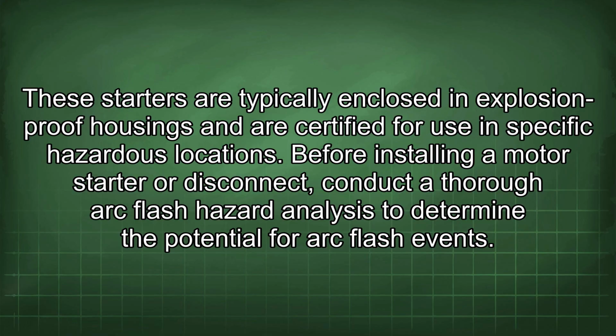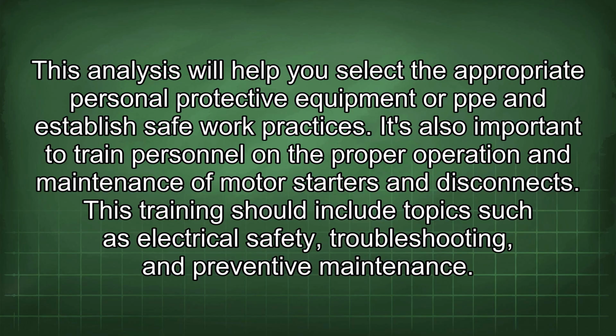Before installing a motor starter or disconnect, conduct a thorough arc flash hazard analysis to determine the potential for an arc flash event. This analysis will help you select the appropriate personal protective equipment or PPE and establish safe work practices. It's also important to train personnel on the proper operation and maintenance of motor starters and disconnects. This training should include topics such as electrical safety, troubleshooting, and preventive maintenance.